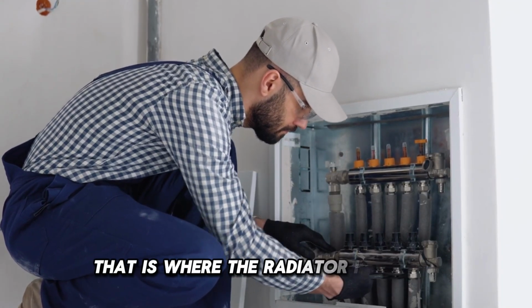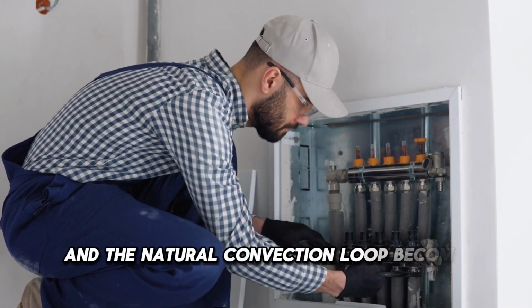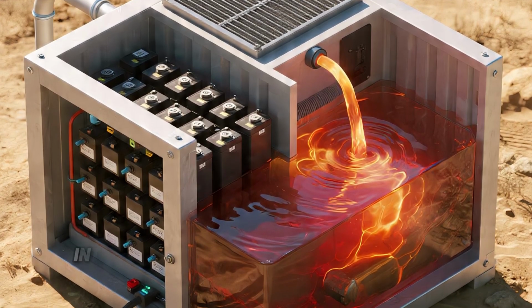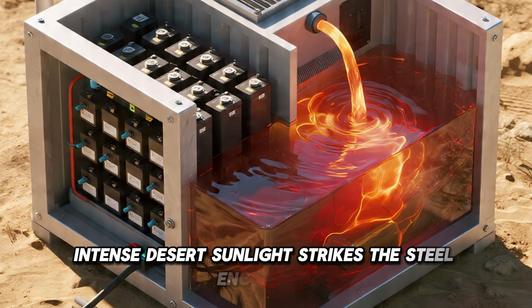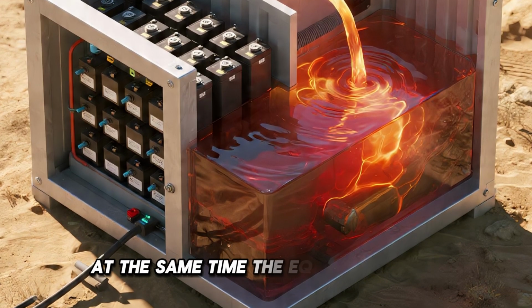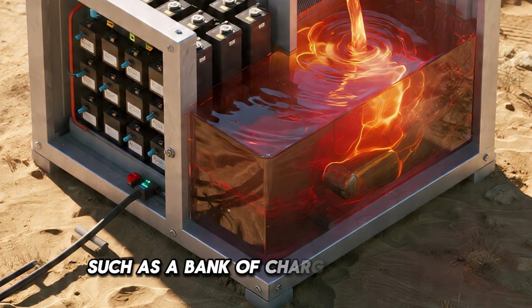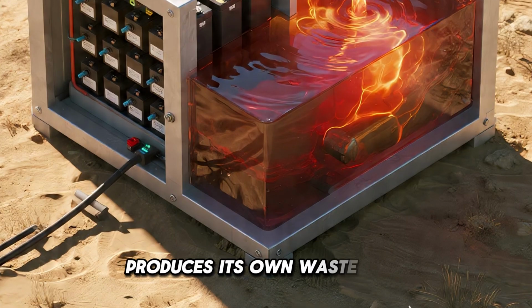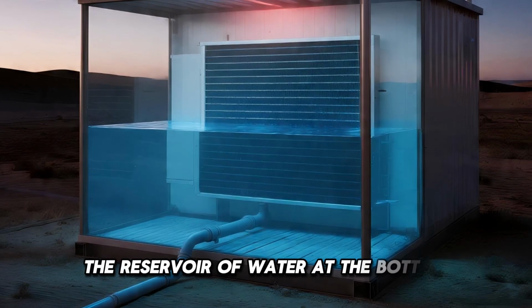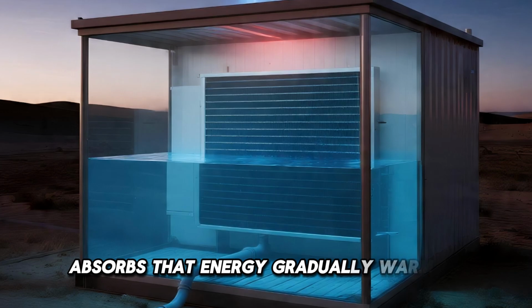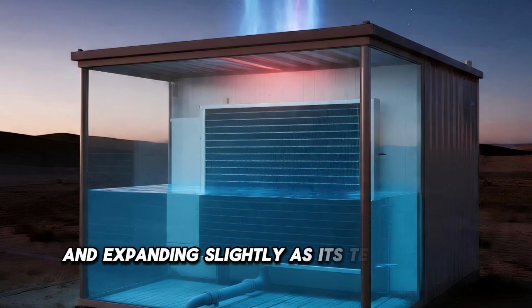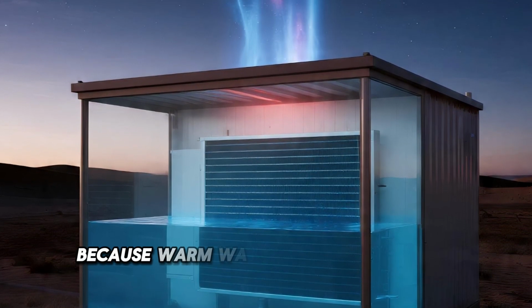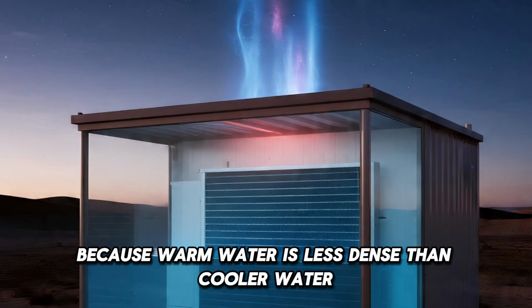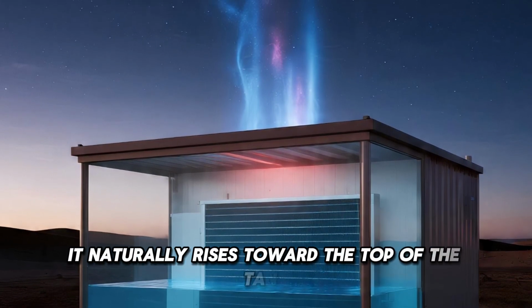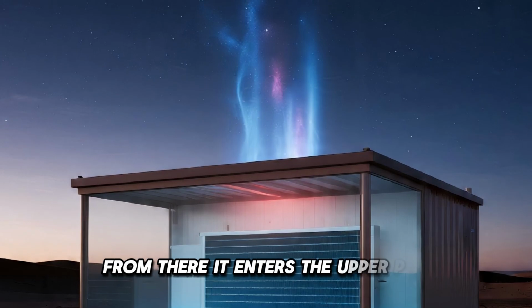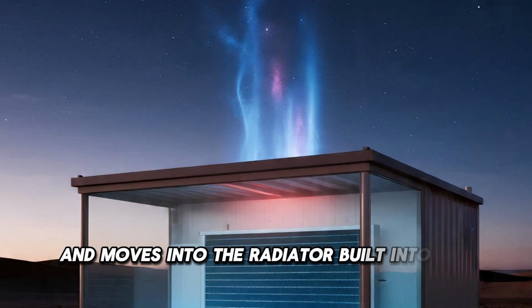That is where the radiator in the lid and the natural convection loop become important. During the day, intense desert sunlight strikes the steel enclosure. At the same time, the equipment inside, such as a bank of charging batteries, produces its own waste heat. The reservoir of water at the bottom absorbs that energy, gradually warming and expanding slightly as its temperature rises. Because warm water is less dense than cooler water, it naturally rises toward the top of the tank, entering the upper pipe and moving into the radiator built into the lid.